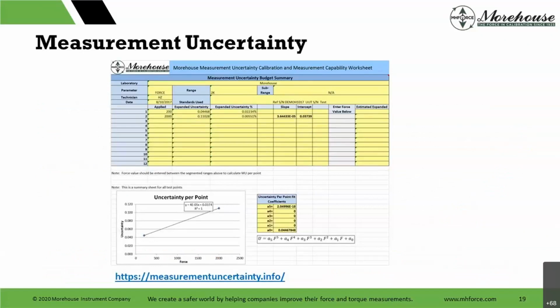So here's a picture, again, from that chat window. Here's a picture of just a down and dirty measurement uncertainty sheet. There are only 2 points here, but you can see the other point here, because this is a live example. When we do this in class, we have people operate our machine. And we typically do 2 to 3 points, because watching someone do repeatability studies is really not the most exciting thing in the world. But if you can talk and have people participate, it's good. And it depends on people's tolerance levels. So with that being said, we usually do 2 to 3 points.